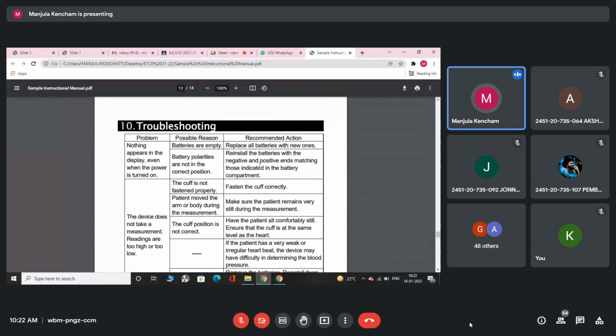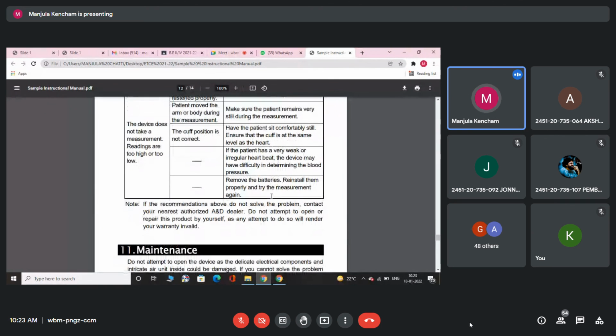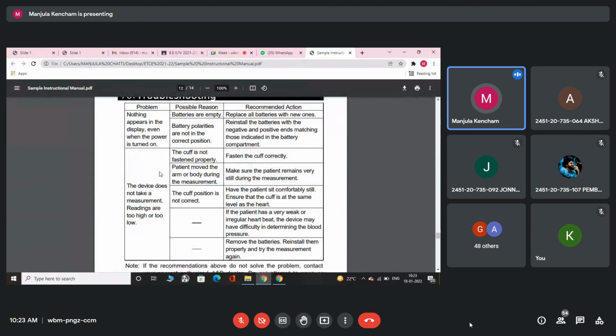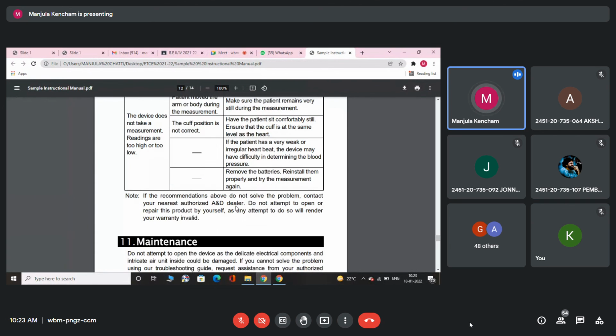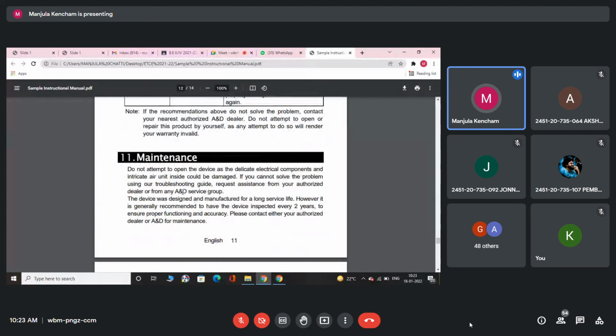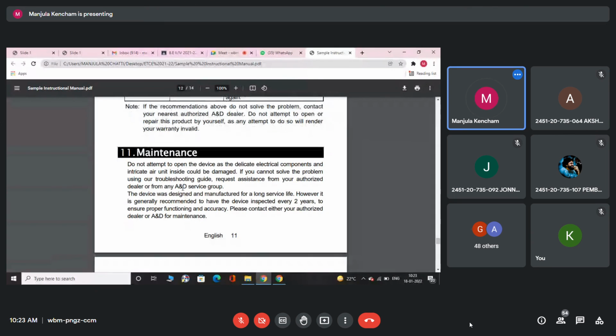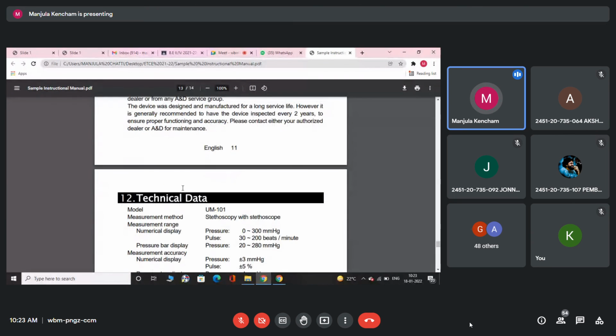Then there are certain troubleshooting aspects. Some problems pop up, and how do I fix them? Problem, possible reason, recommended action. Nothing appears, batteries are empty, replace all the batteries. Device does not take a measurement, readings are too high or too low. The cuff is not fastened properly. Patient moved the arm. The cuff position is not correct. That's when this particular problem arises. So fix it accordingly. Maintenance of the machine or the equipment. It has to be serviced once in 2 years, something like that.